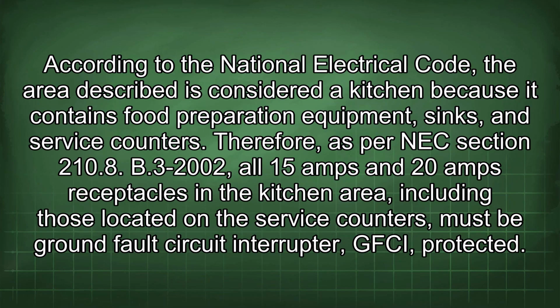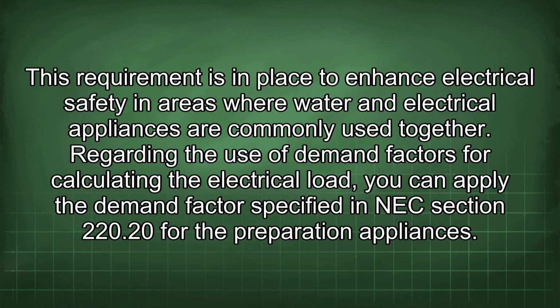According to the National Electrical Code, the area described is considered a kitchen because it contains food preparation equipment, sinks, and service counters. Therefore, as per NEC Section 210.8(B)(3)-2002, all 15 amp and 20 amp receptacles in the kitchen area, including those located on the service counters, must be ground fault circuit interrupter (GFCI) protected. This requirement is in place to enhance electrical safety in areas where water and electrical appliances are commonly used together.